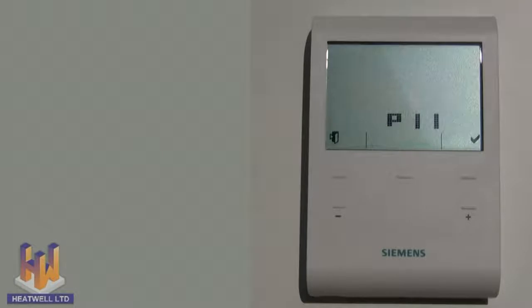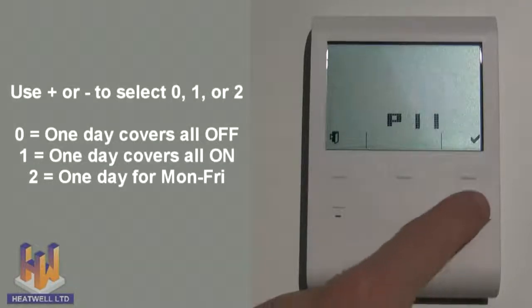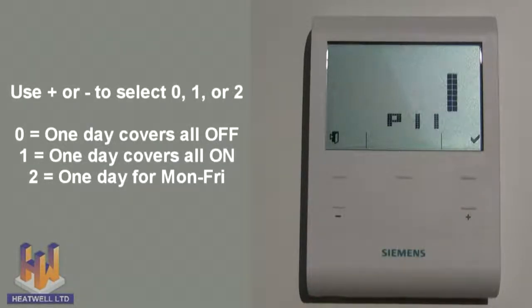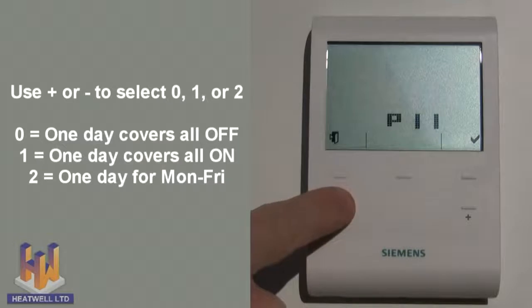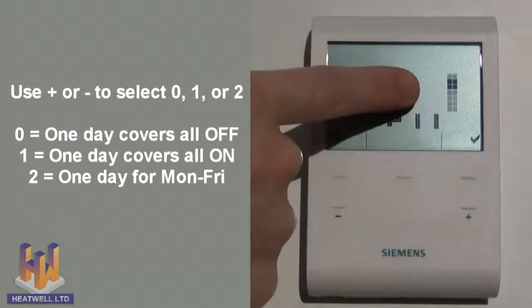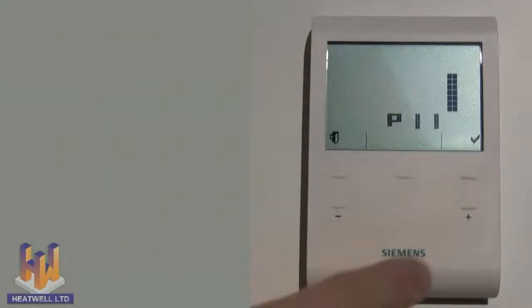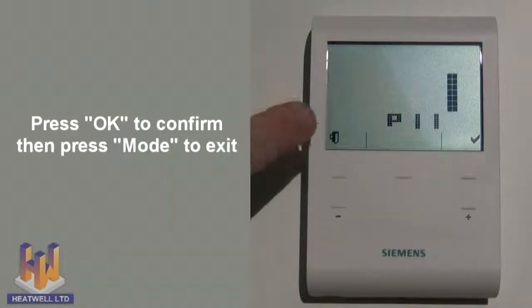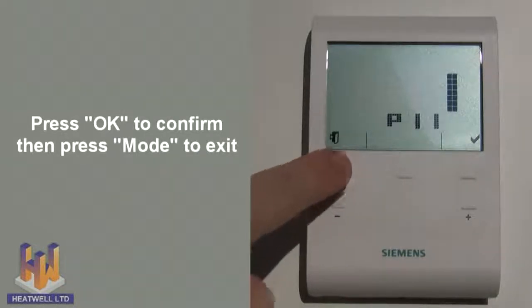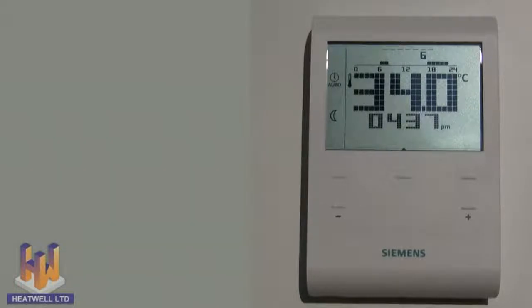Now use the plus or minus buttons to change between 0, 1 and 2. 0 means this option is turned off. 1 means it's turned on. 2 is a different option where the unit will use the same temperature for only 5 days and a different temperature for Saturday and Sunday. In this case, we will select 1. Press OK to confirm, and then press the mode button to exit. Now you can enter on and off times for just 1 day, and these times will automatically apply to all other days of the week.